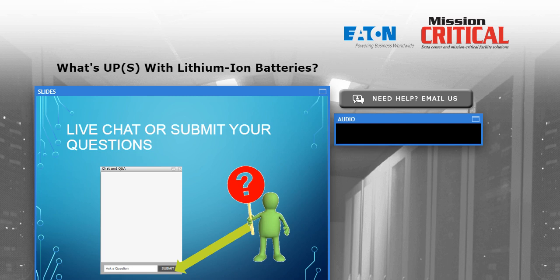What is the main feature that makes a lithium battery safe? The main feature that makes it safe is the battery management system. Now, there's other mechanical things that we do basically to make sure that the battery plates never short together. Use a high-strength separator, put a barrier around the perimeter of the battery in case it swells or gets dropped. But the battery management system basically ensures that that battery will not get itself in a position where it generates more heat than it can dissipate. That's the definition of thermal runaway. So the battery management system ensures 24/7, 365 that that battery can always dissipate more heat than it creates. As long as you do that, you will not have a thermal event.